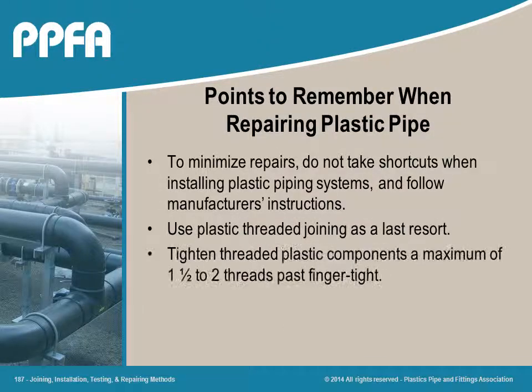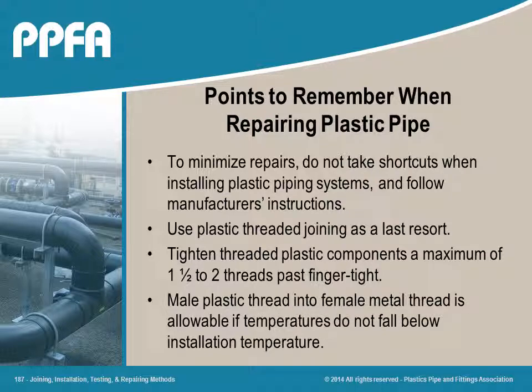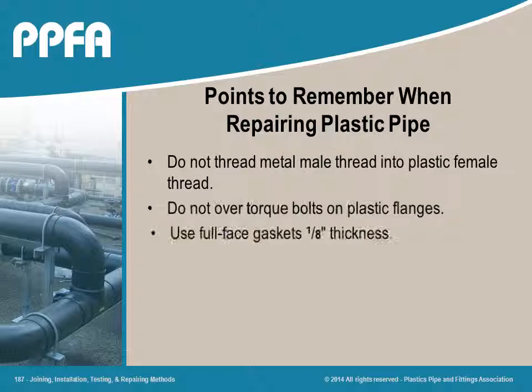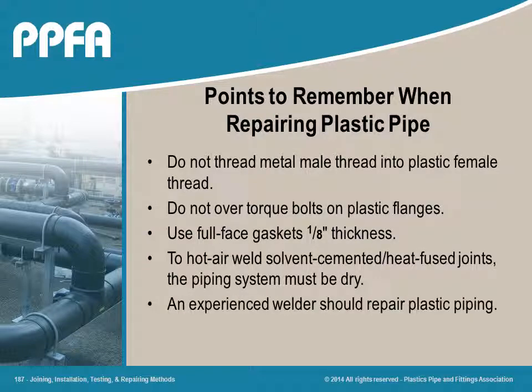Use standard repair methods for threading, flanging, and other mechanical joints. Inline repairs of solvent cemented or heat fused systems should only be implemented if there are very small leaks. If larger leaks occur, remove the entire leaking joint and replace with new piping products.